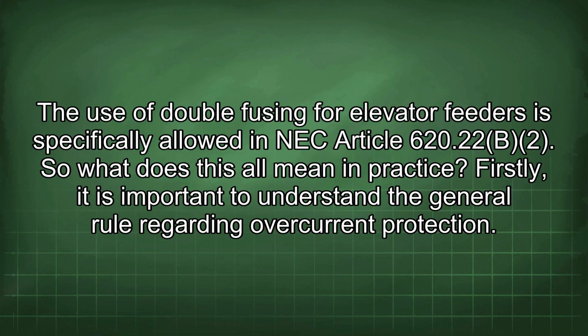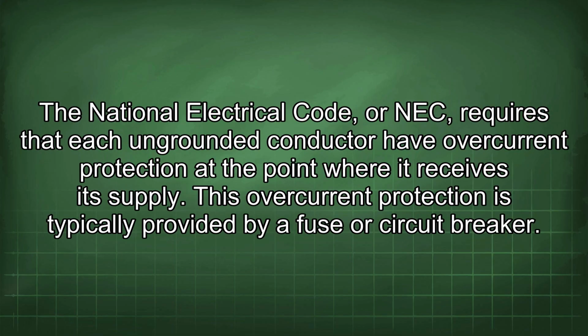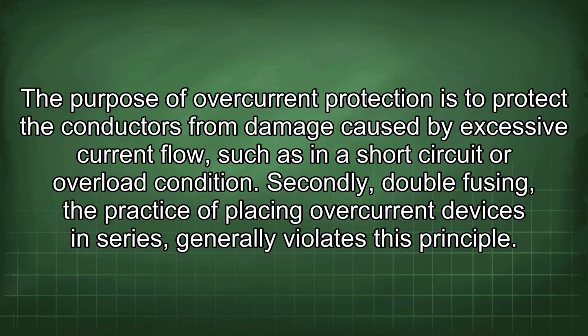Firstly, it is important to understand the general rule regarding overcurrent protection. The National Electrical Code, or NEC, requires that each ungrounded conductor have overcurrent protection at the point where it receives its supply. This overcurrent protection is typically provided by a fuse or circuit breaker. The purpose of overcurrent protection is to protect the conductors from damage caused by excessive current flow, such as in a short circuit or overload condition.